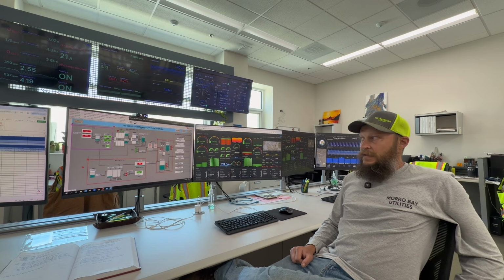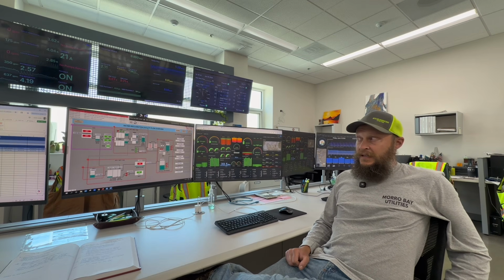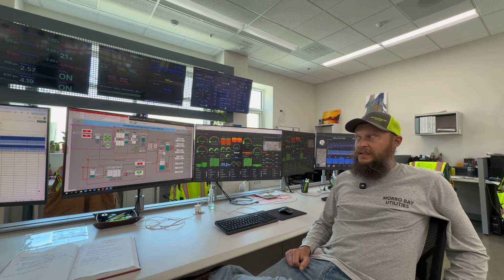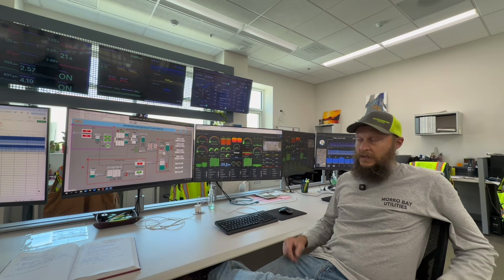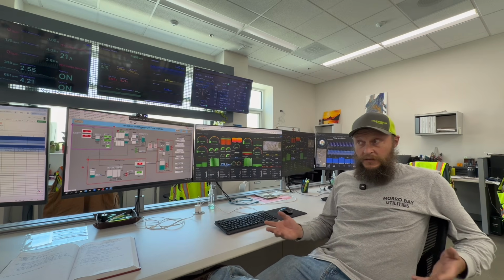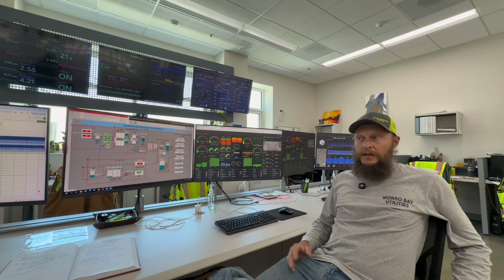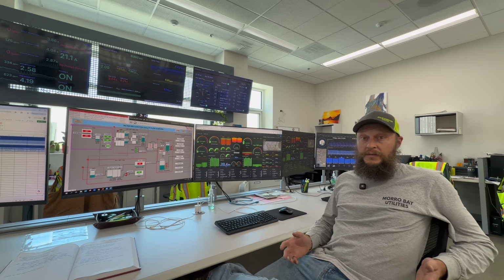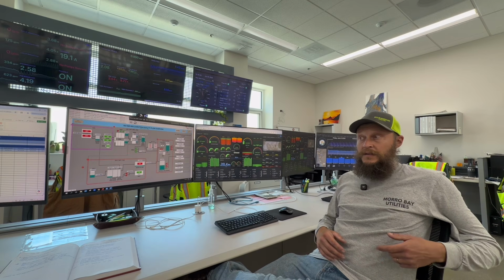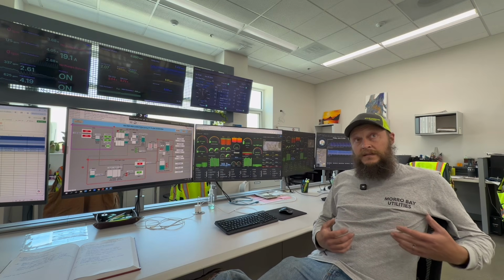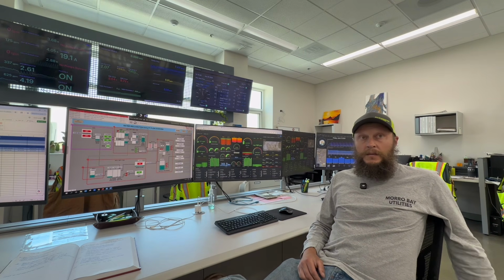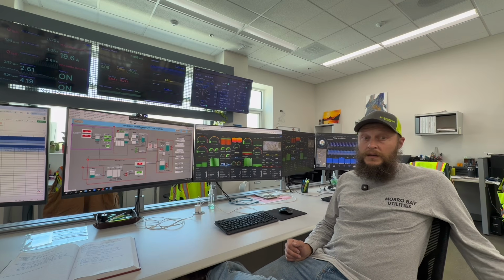Sure. So the HMI, human machine interface, is the screens that you interface with the control system. If I need to check how a piece of equipment is running, I can look at the HMI and control it at that level. SCADA is an acronym for Supervisory, Control, and Data Acquisition. It's more than just a screen—it's a system that allows us to visualize the plant, control the entire plant, collect data from it, and then visualize that for process control or for compliance.